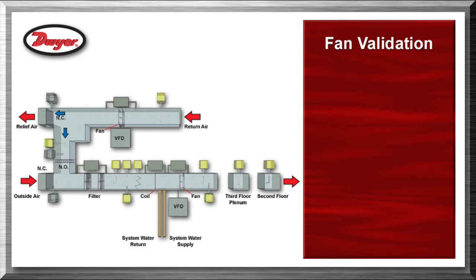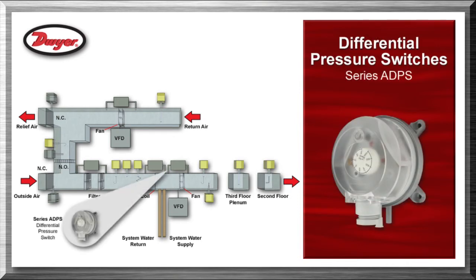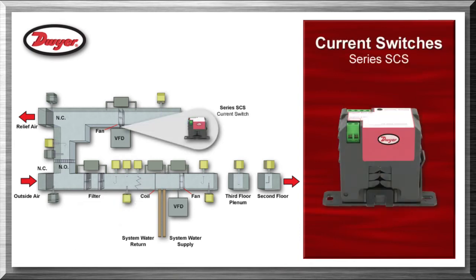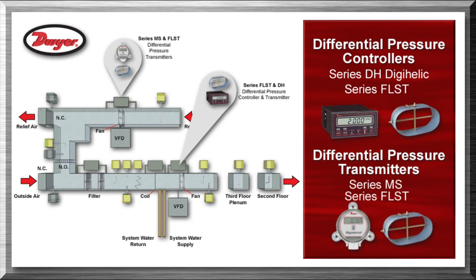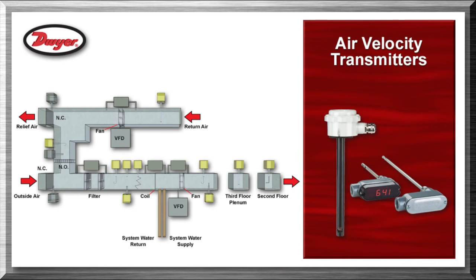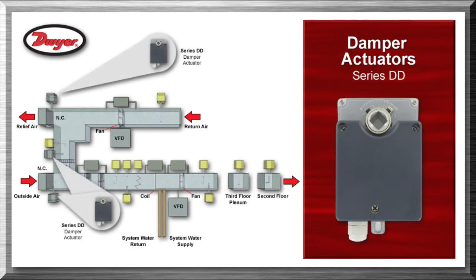Dwyer offers several products that can be used for fan validation, proving the fan is operating. Differential pressure switches series ADPS are used by monitoring the differential pressure between upstream and downstream of the fan. Current switches series SCS are used by monitoring the current usage of the fan. Differential pressure controllers series DH Digihelic or differential pressure transmitters series MS are used with an airflow station, such as the series FLST, to monitor the airflow rate exiting the fan. Air velocity transmitters series 641 or series AVU are used to monitor the airflow rate exiting the fan. Damper actuators series DD are used to open and close dampers to change the airflow through the air handler.